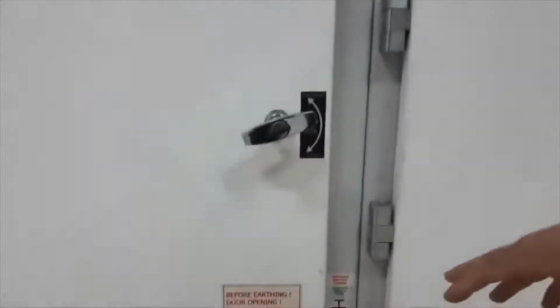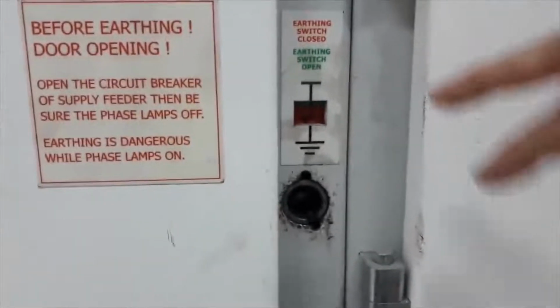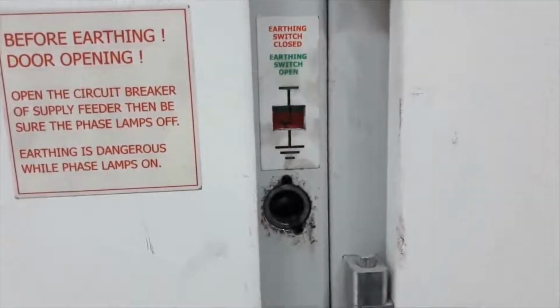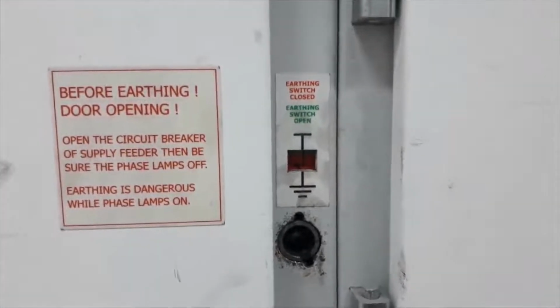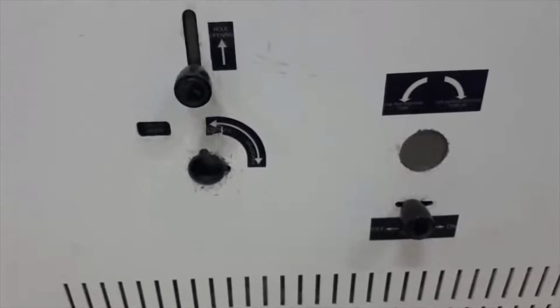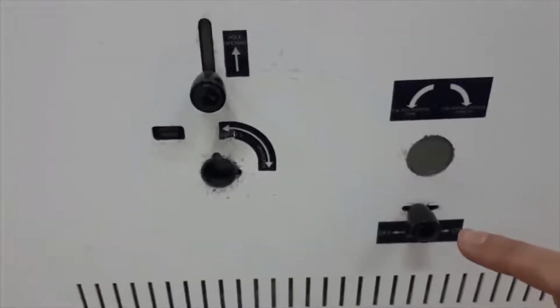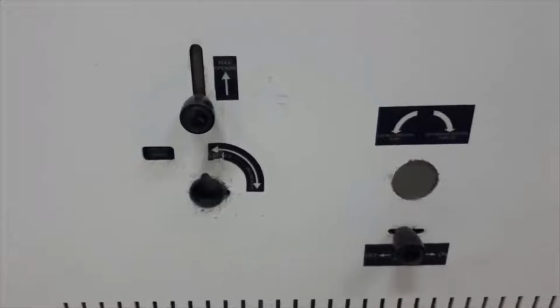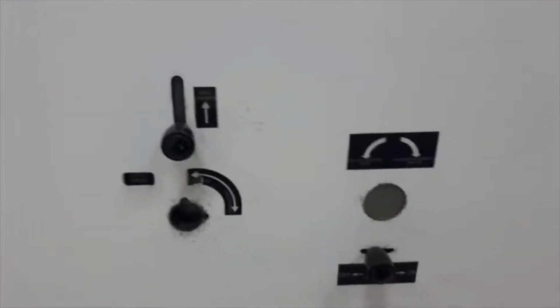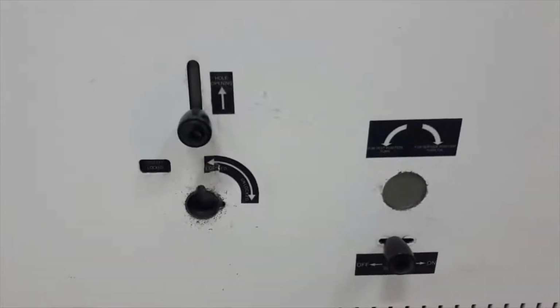Here is where the handle is placed inside the panel, by which we can open or close the ground disconnector. This handle is for ground disconnector. Okay, here also a handle can be placed inside, by which we can put the breaker in test or connect position. They work together with this latch. When we press the latch, the handle can be inserted and the breaker might be put in test or connect positions.